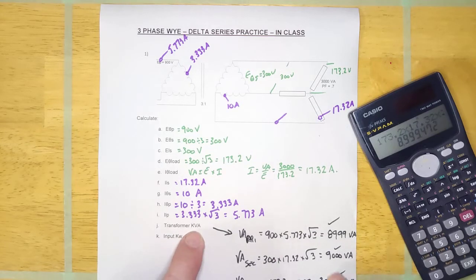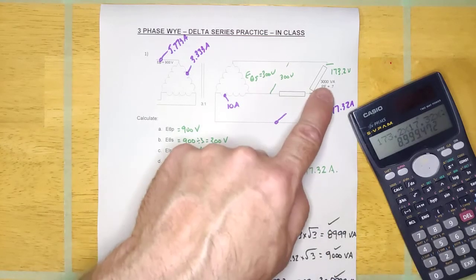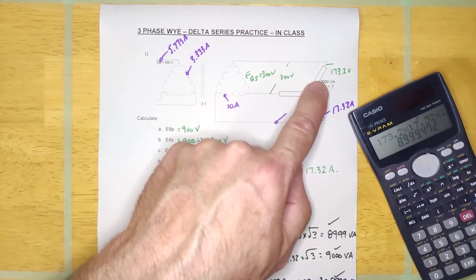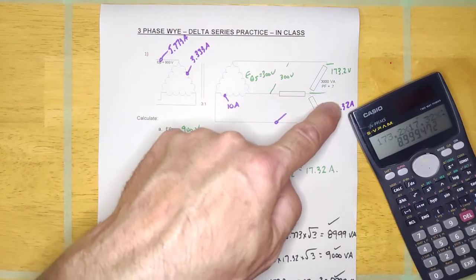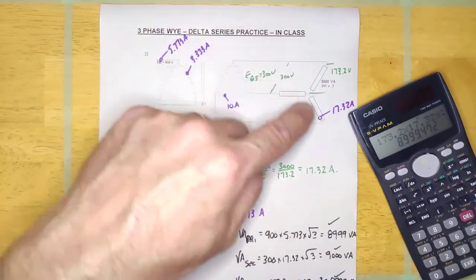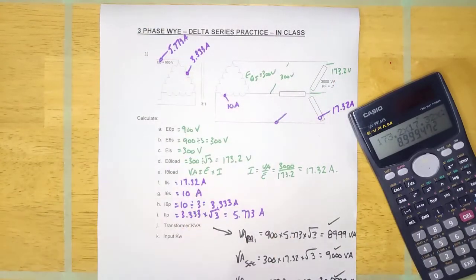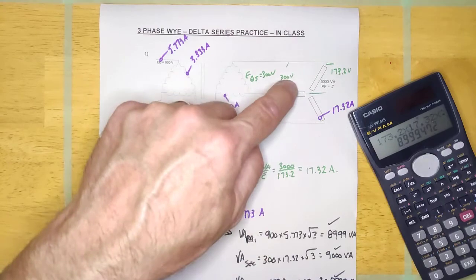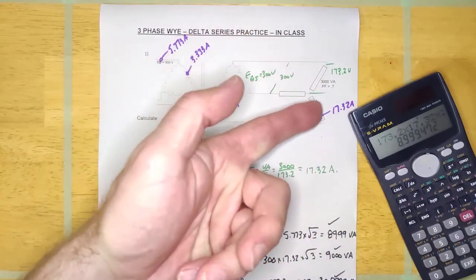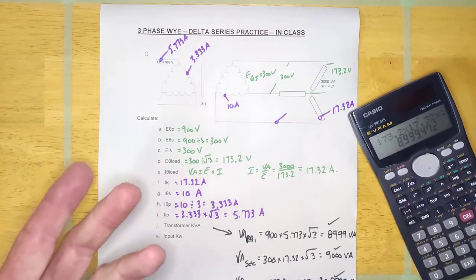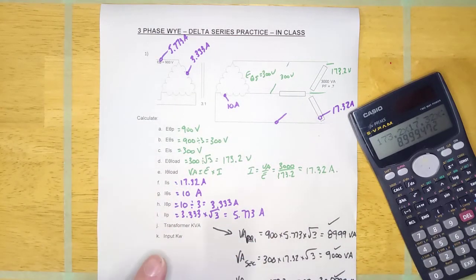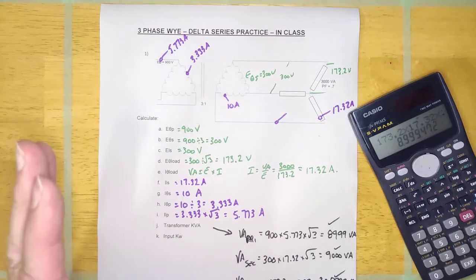Notice it's 9000 VA total. Also notice that each load is 3000 VA, and 3000 × 3 adds up to 9000 — that's another way to check it. Those three 3000 VA loads are what's determining the volt-amps of this entire circuit, and there are three of them, which adds up to 9000. It works every way.